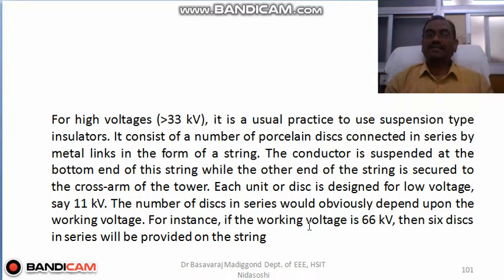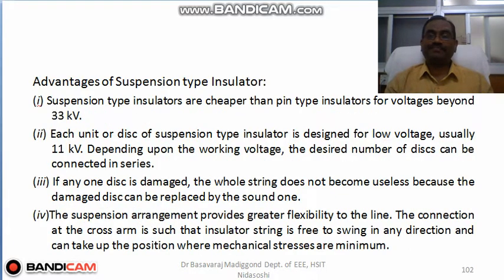The number of discs in series would obviously depend upon the working voltage, right? For instance, if the working voltage is 66 kilovolts, then we require 6 discs in series. So it all depends on working voltage. Okay. What are the advantages of suspension type insulator?